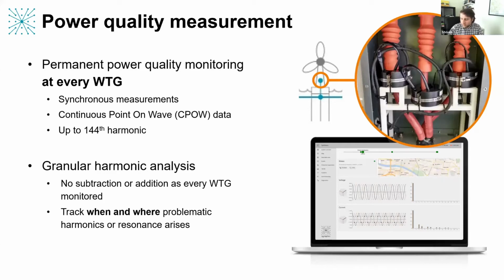For example, one turbine might be experiencing some issue, maybe a control issue, which means it's injecting more harmonics than its neighboring turbines on the same string, and we can pick that up with this granular monitoring and immediately highlight it. Whereas some of those interactions, due to being in phase or anti-phase, might actually cancel out. So you might not see that there's a problem if you're only monitoring at one location or a limited number of locations. It means we can very quickly see when there's a deviation and pinpoint where it's actually happening.